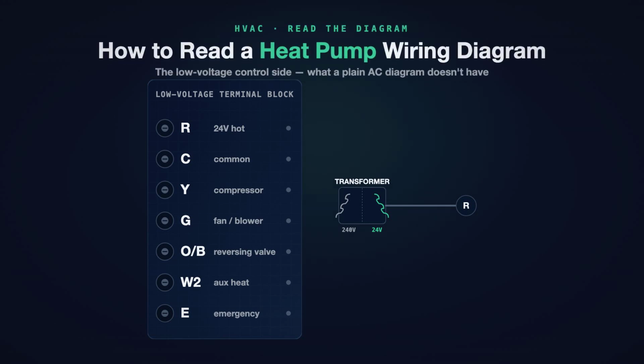This is a heat pump wiring diagram, and by the end of this video, you will read one at a glance. Look at the low voltage terminal block: R, C, Y, G, O or B, and W2. Watch me trace the very first wire, R, the 24-volt power, straight off the control transformer.